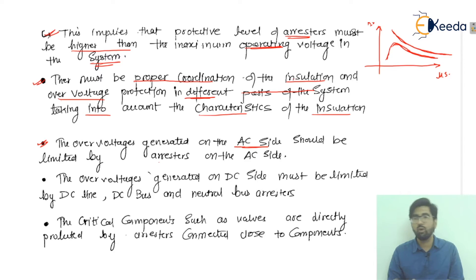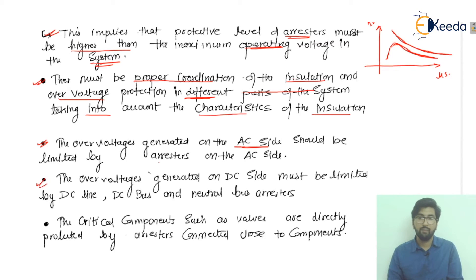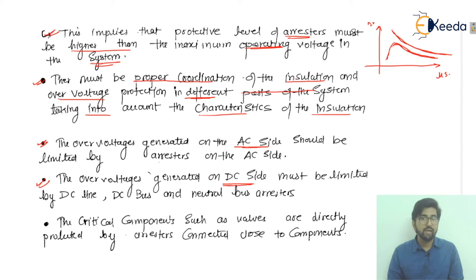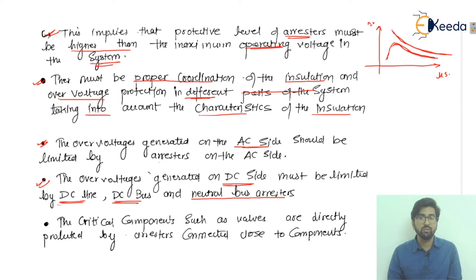If overvoltage is generated on the AC side, it can be limited or permanently removed by the arrestors connected on the AC side. Overvoltage generated on the DC side must be limited by the DC line arrestors, the DC bus arrestors, and the neutral bus arrestors.